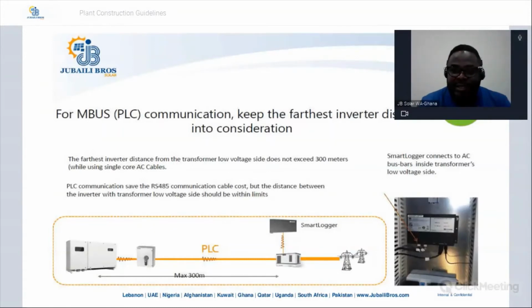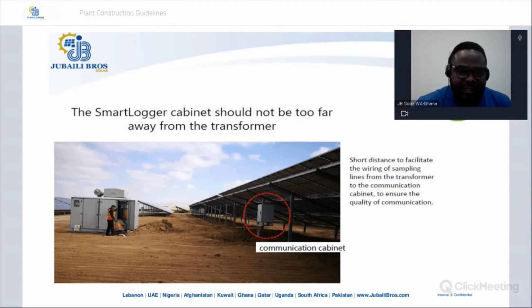But all you have to make sure is that the distance between the last inverter and the smart logger should not be more than 300 meters, or else you'll be losing some communication signal and strength. This information again is very, very important. Let's move to the next.